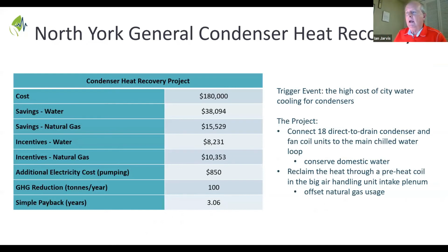We've got 4 early stage projects for your consideration that help illustrate this. With North York General Hospital, the trigger event there, and I say that's a key term, the trigger event is the high cost of city water. They actually have direct to drain condensers. The assumption was that they would convert those to air-cooled condensers to save the city water. Instead, they've connected them as water-cooled condensers to the chilled water system and recovering the heat directly into an outside air plenum that picks up a number of air handling units. So this is direct heat recovery, and you can see the economics that play out with that.